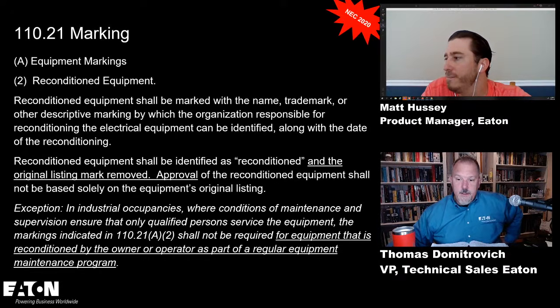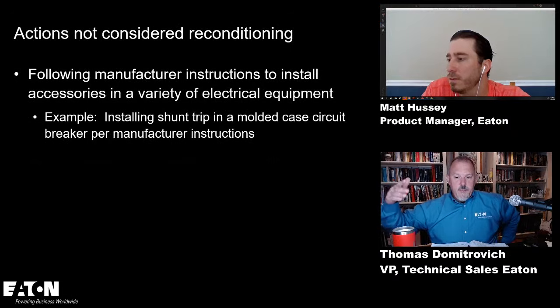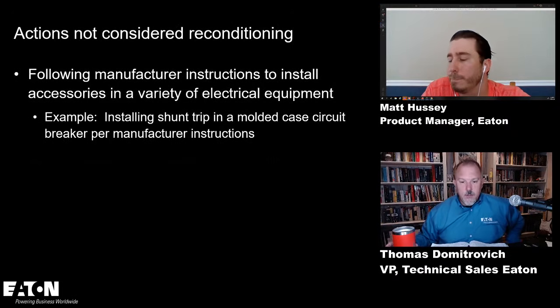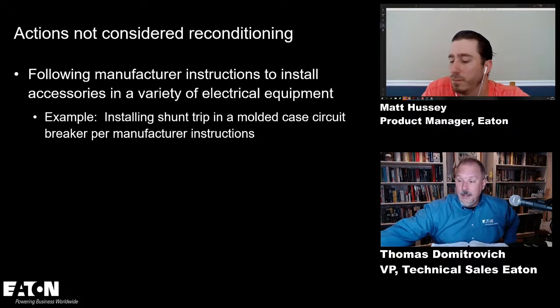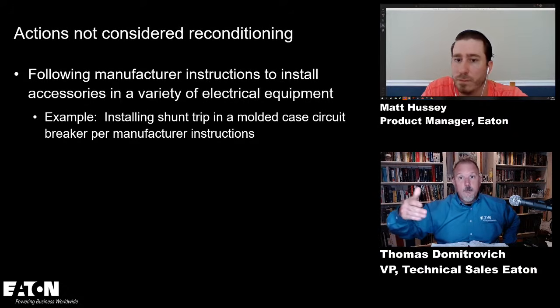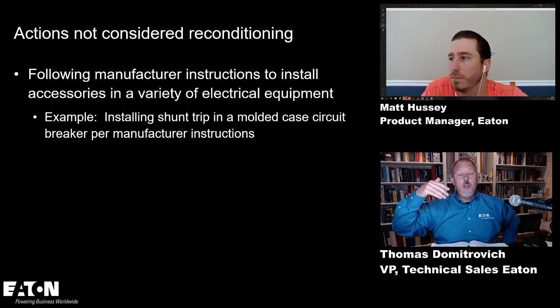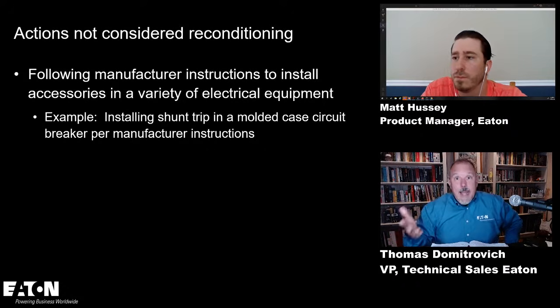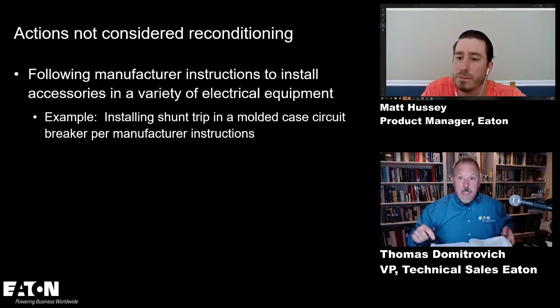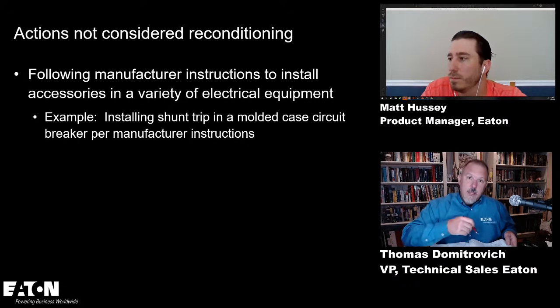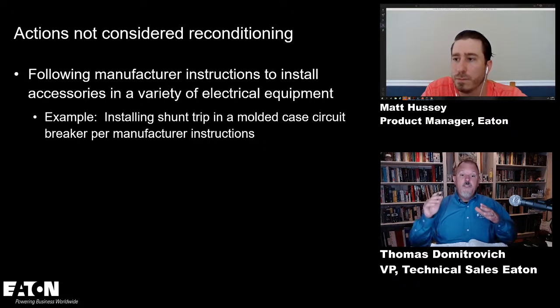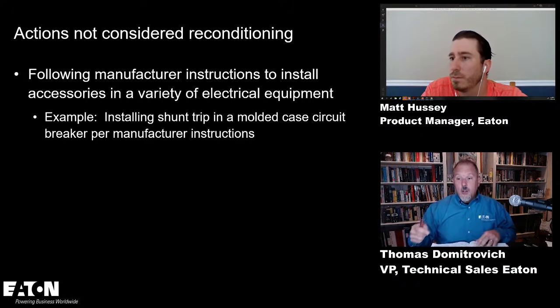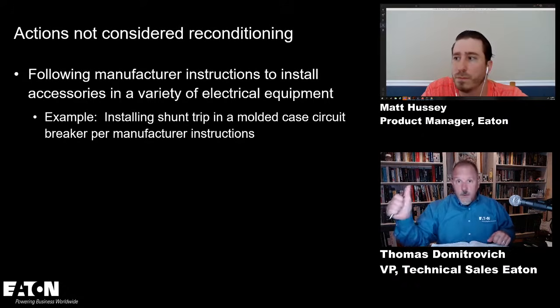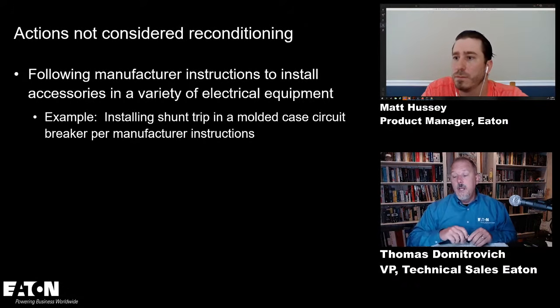Yep. And then finally, following manufacturer's instructions to install accessories and a variety of electrical equipment is not considered reconditioning. And again, even though there is nothing in 430 that says you cannot recondition, it's telling you that you can per the NEC, but then you would have to go back to the definition and understand whatever you do to that equipment, if it's considered reconditioned, and then go to 110.21 for the marking requirements to say you've got to remove the listing mark, put your name on it, and do all that kind of stuff. And that's for traceability and transparency reasons, basically.